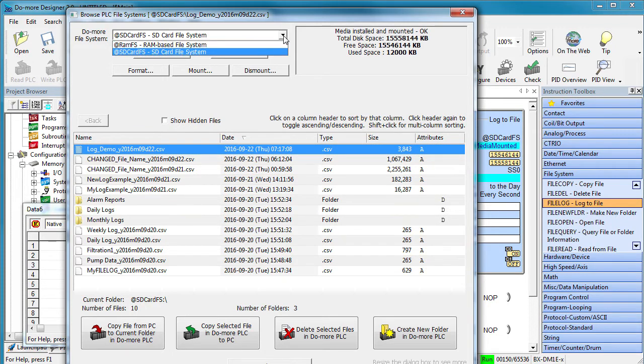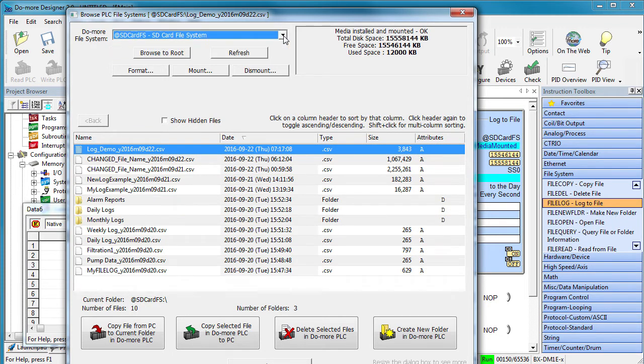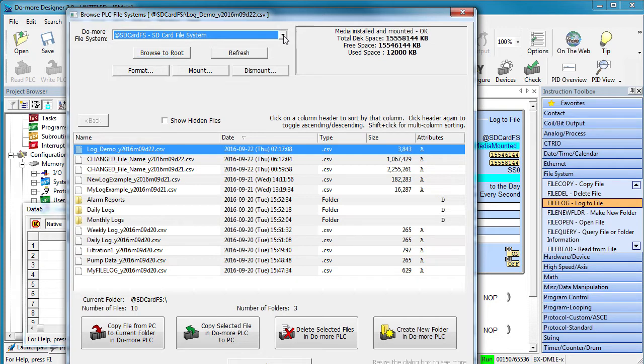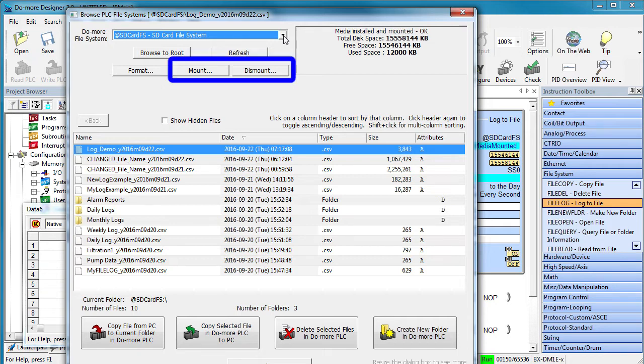Refresh updates this list if you insert an SD card while the dialog is up. This is for formatting the RAM drive. You can't format the SD card here because it would take forever on the PLC. So, for SD cards, just format them on your computer before using them here on the PLC. You can also mount and dismount the SD card.